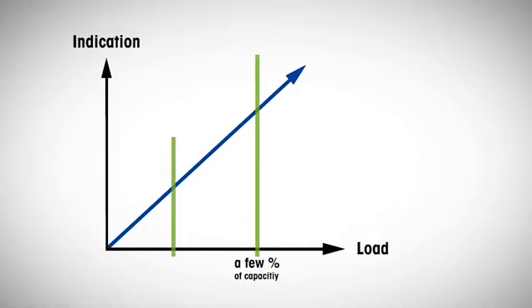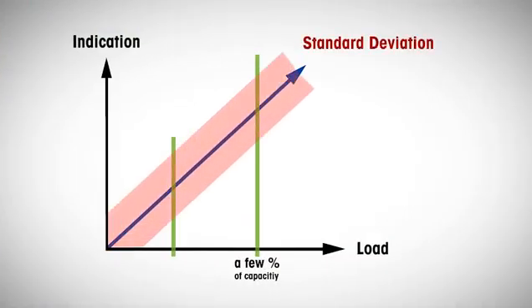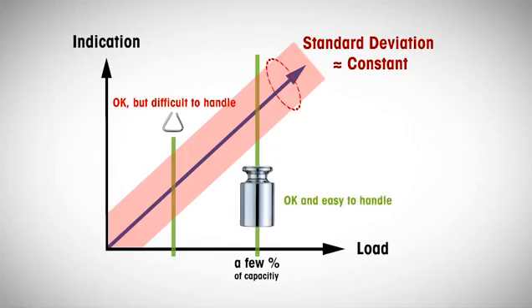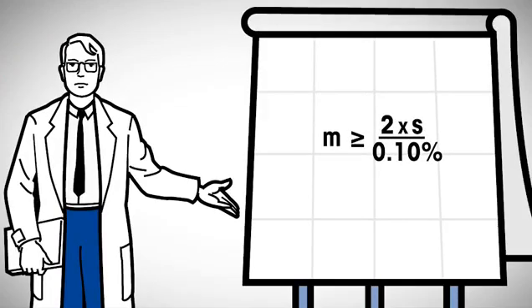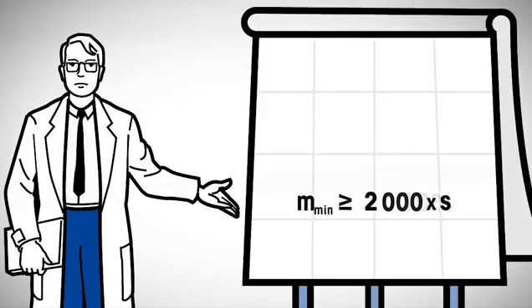USP states that the standard deviation is virtually independent of the sample mass at the lower end of the weighing range. Hence, a test weight of a few percent of the balance capacity can also be used to assess repeatability and derive the minimum weight from this formula.